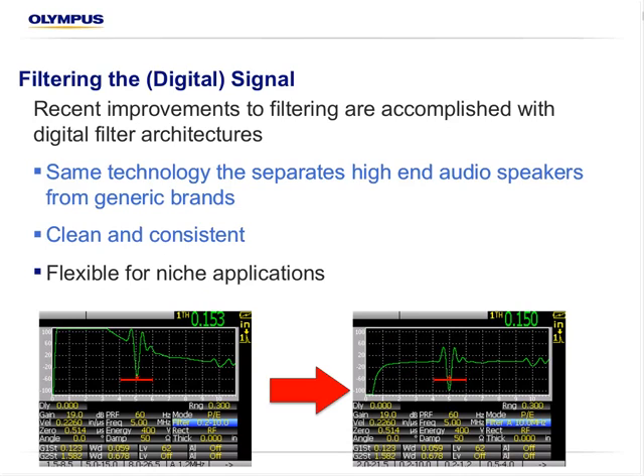So here at Olympus, we've had several customers that have come to us over the years that have needed those more customized, more focused narrowband filter sets. And with this technology, we've been very readily able to supply that. And in fact, all that's needed is really to program these filters, again, using math, basically using algorithms, that can get added to the firmware, to the code that goes into the flaw detector, and it can be emailed or sent through the web so that a simple upgrade of the unit will now allow access to those filters.